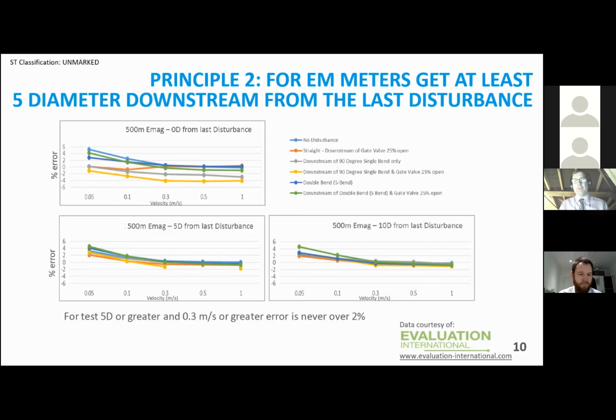They then moved that EMAG meter to 5 diameters downstream, so 2,500 millimetres, and we see that the errors got smaller. They then moved it 10 diameters downstream, so 5,000 millimetres from the last disturbance, and the errors got a very, very tiny bit smaller. So my takeaway here is that if you put your meter at 0 diameters, you could have relatively large errors, but for an EMAG meter, just get 5 diameters downstream and the errors will reduce greatly. If you go to 10 diameters, you'll get some benefits, but they are very, very marginal.